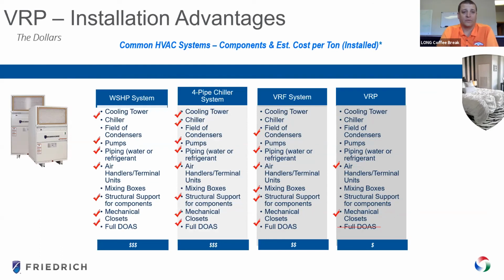And this slide generally just talks about the various needs of common systems that we're seeing and the complexity involved. Also at the bottom, you can kind of see the dollar signs in terms of what these systems typically cost. When you're doing a heat pump system, you're paying for your individual compressors, in addition to your condenser pumps, your cooling tower, air handlers, and a full DOAS. So that generally drives your cost pretty high, similar to a 4-pipe system. With a VRV, you're able to minimize typically how much ductwork you're bringing in, but you still have additional complexity and a system that ends up costing a little bit. Where the VRP kind of finds that sweet spot of still being able to bring in outside air and provide a comfortable space while driving down first cost for the owner.